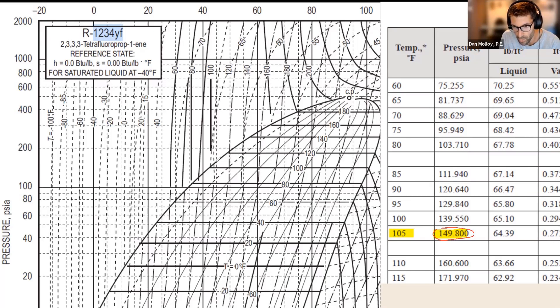Well, it'd be about a quarter of the way above and probably more like here. And previously we were thinking it was more like here. So now we'll go vertically up from that location and it's looking like it's more around 45 BTU per pound instead of 42, 43. So we just brought a little bit more accuracy to the solution than we otherwise would.